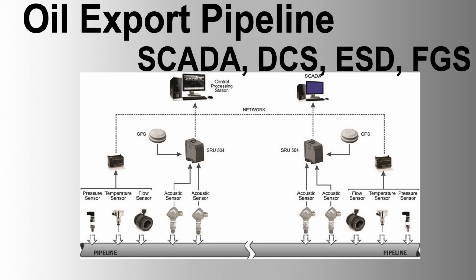4. Fire and Gas Detection System, FGS. Function: detect and respond to fire and gas presence to protect human life and pipeline infrastructure. Design aspects, independence: standalone, fully addressable, redundant system design. Objectives: prevent and protect from serious damages due to confirmed fire and gas presence. Functions: fire and gas monitoring and control, continuous monitoring of detectors, communication with ICS for secondary actions. Interface: fire and gas data displayed on dedicated ICS graphic displays, maintenance bypasses applied through ICS HMI.